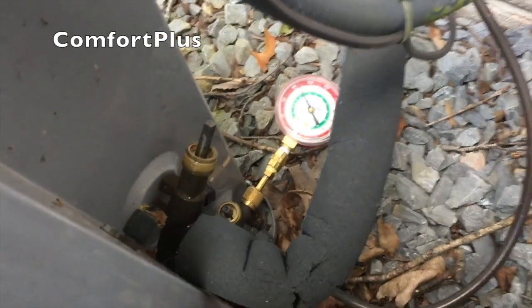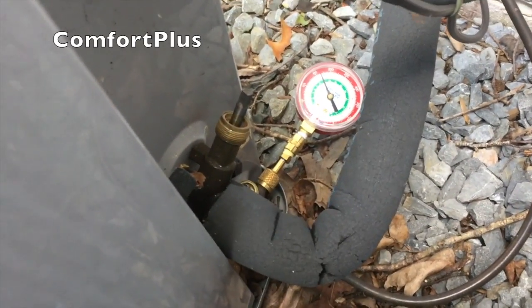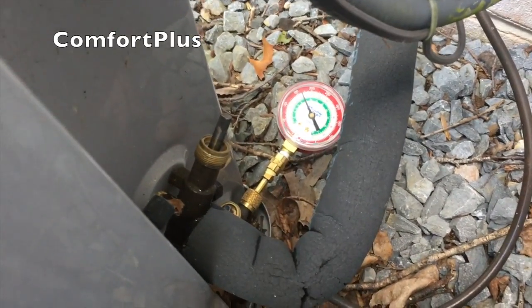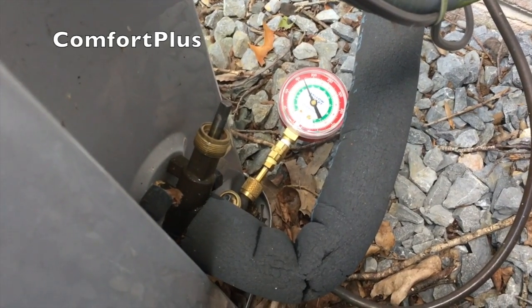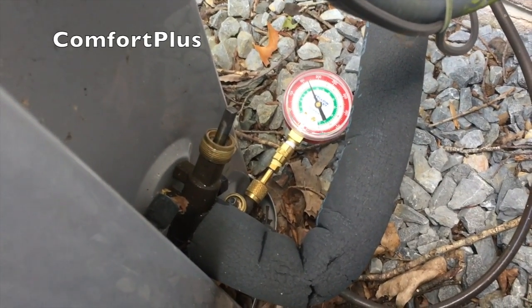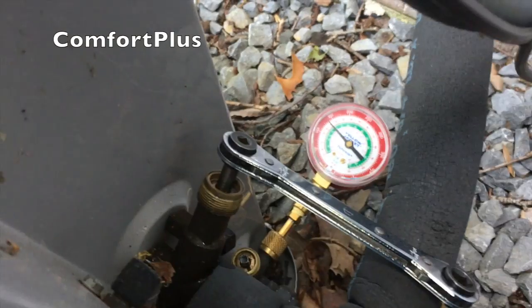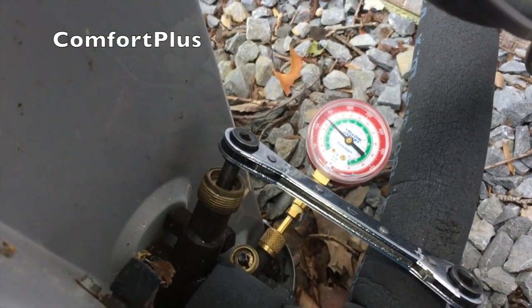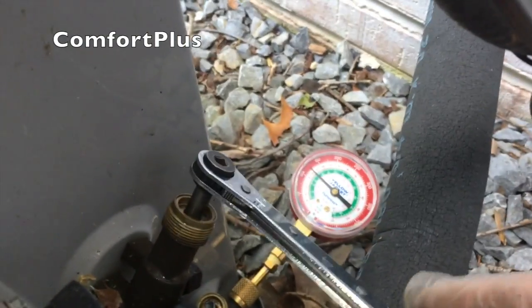I'm just going to pump this guy down using my Z manifold. I'm going to leave this unit. I'll extend the line set on out to the garage after I get through with this install and get me some cooling out there. Shut off the liquid valve, it's starting to drop. I've got the suction valve started. Got my disconnect open so I can pull it out when it gets down there.